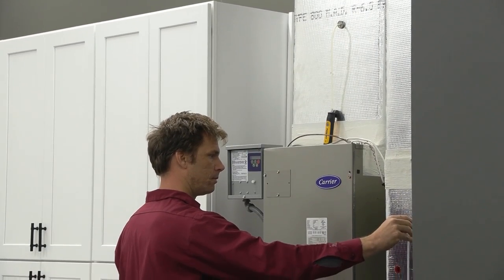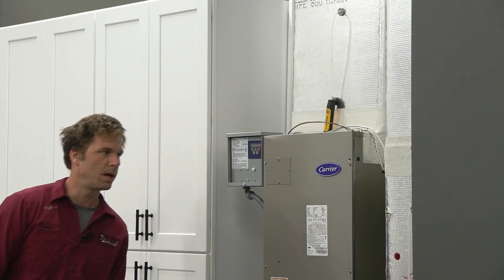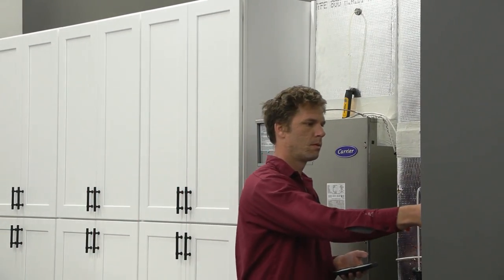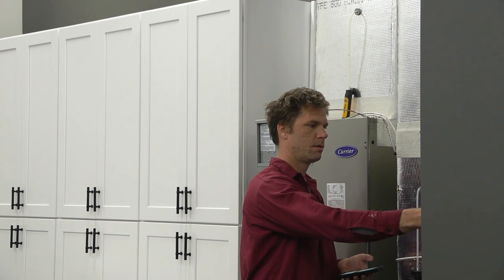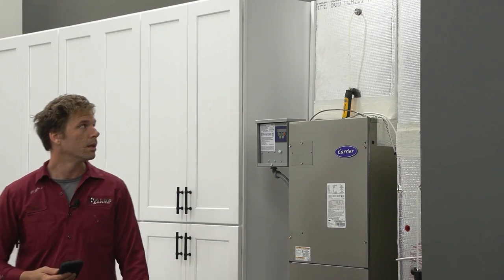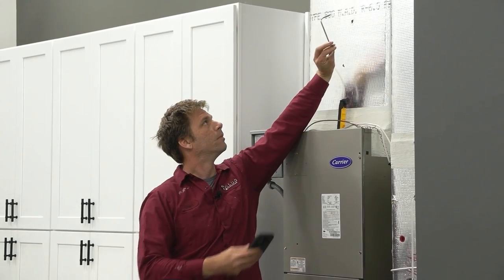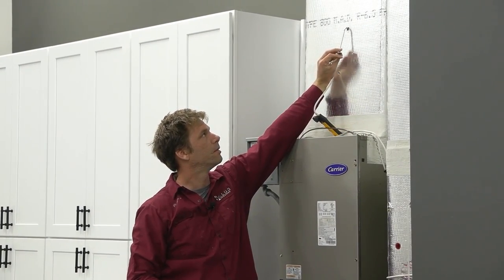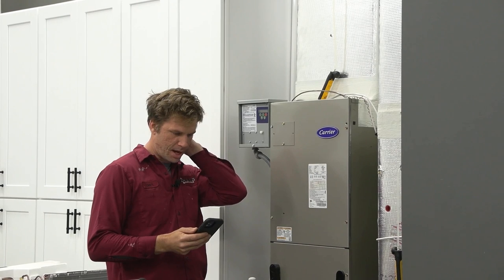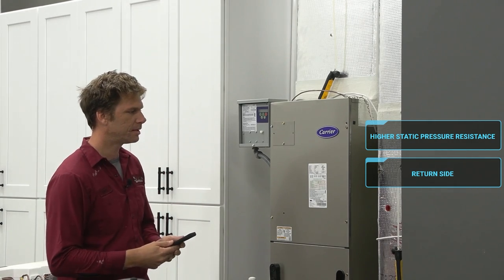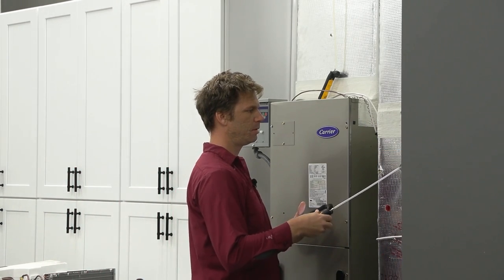I installed it before the filter. Let's go ahead and look at our static pressure. This thing is refusing to run in full stage yet. The arrow needs to point in the direction of the airflow. We have a higher static pressure resistance on our return side, but this is still before the filter. So let's just compare when we move that.